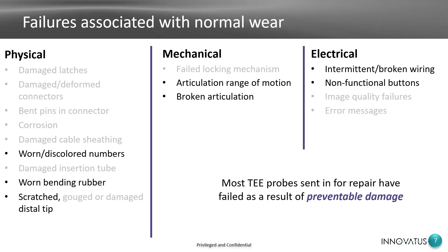And so we can get intermittent or broken wiring or non-functional buttons because those buttons are mechanical. Most TEE probes sent in for repair have failed as a result of preventable damage. So let's look at preventable damage. Most TEE probes sent in for repair to Innovatus have failed as a result of gross fluid invasion. Gross fluid invasion is the most catastrophic type of failure we'll get with TEE probes. It's also the most preventable.